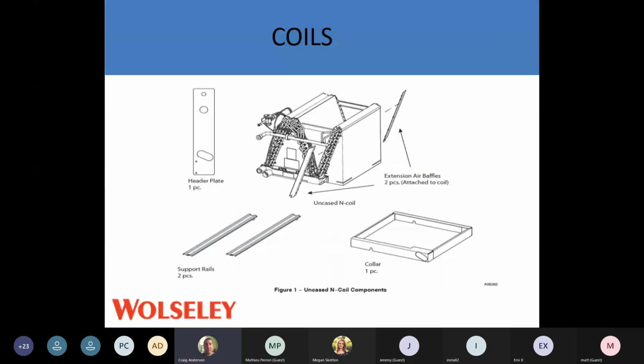So I like to go through the N coil. I get a call probably a dozen times a year that the air conditioner's freezing up outside. Pressures are good, I leave, and it's freezing up. So we have to be very mindful of the N coil because of airflow. The N coil underneath has two openings. It has an opening where the A part is on the coil, and then on the right-hand side where the N part goes on the coil, there's an opening under there too. That opening's about 1.5 inches.